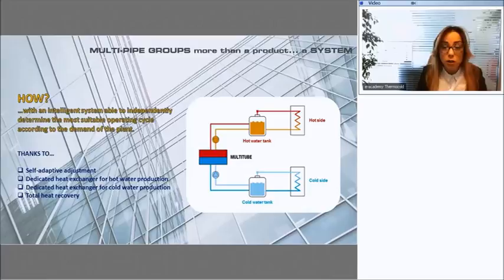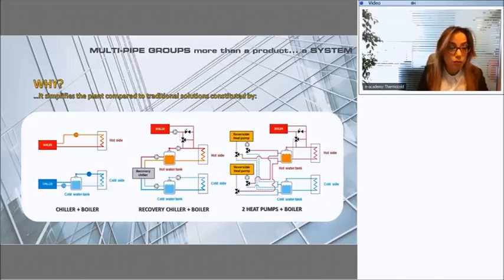So the unit, let's say, is split in 2 separate water sections. One always dedicated to cooling and the other always dedicated to heating. Thanks to the total heat recovery mode, the unit is able to produce simultaneously hot and cold water by recovering all the condensing heat in the heat recovery heat exchanger. So it means that the condensing heat is not dissipated through the condensing coil, but it is recovered in a plate exchanger or a shell and tube exchanger in order to produce the required heating capacity.